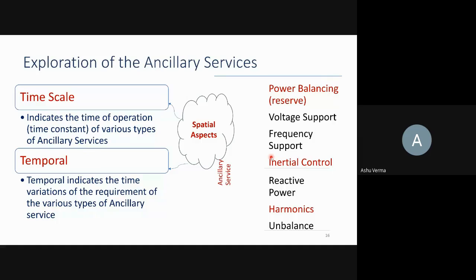This automatic generation control may have primary response, secondary response, and tertiary response. This response provides inertia to the system to keep the frequency within range. That is the natural inertia available because of synchronous generators.